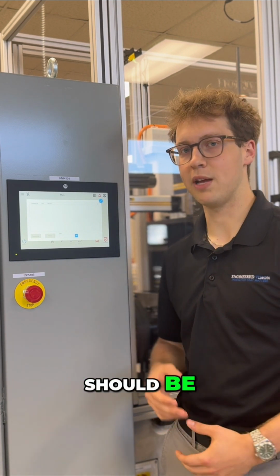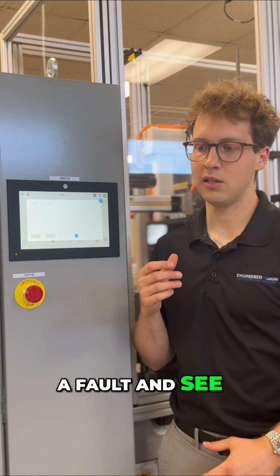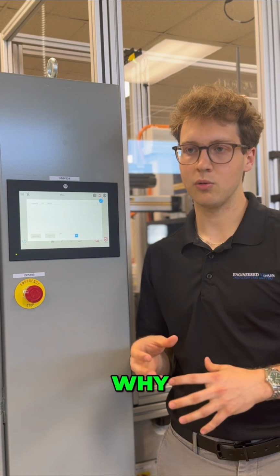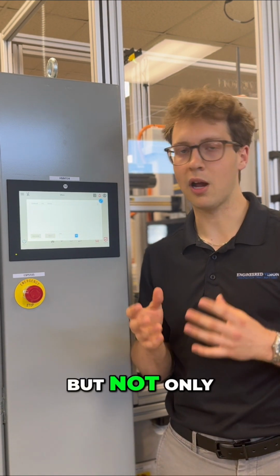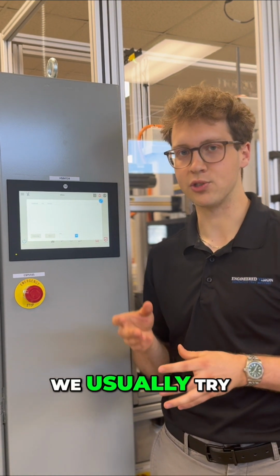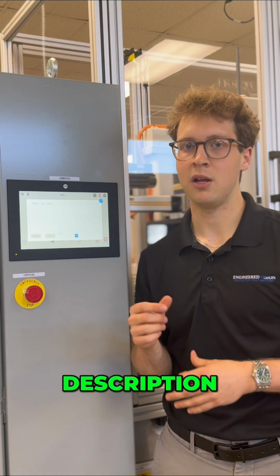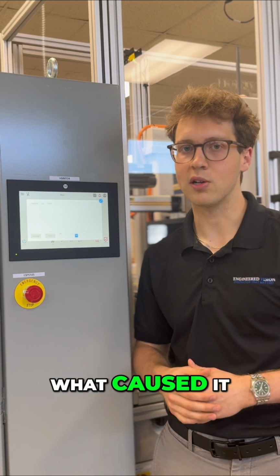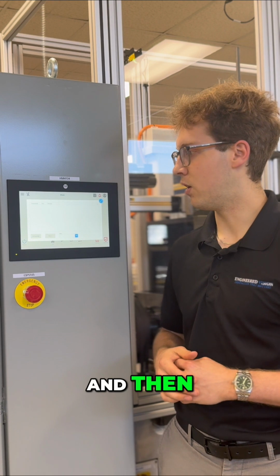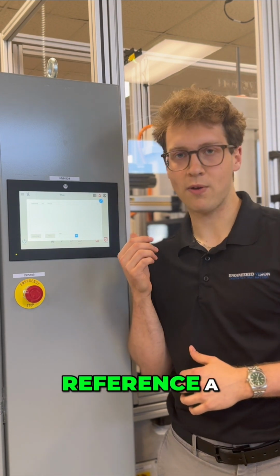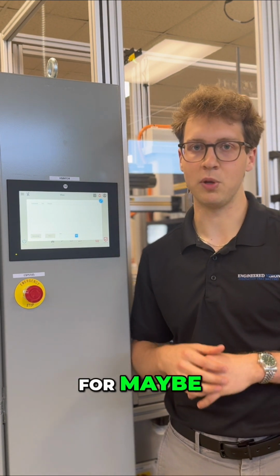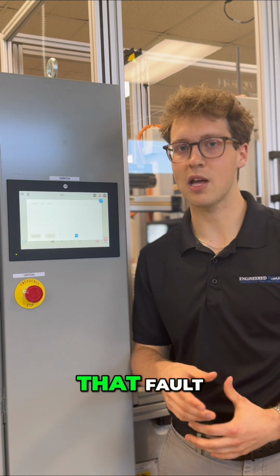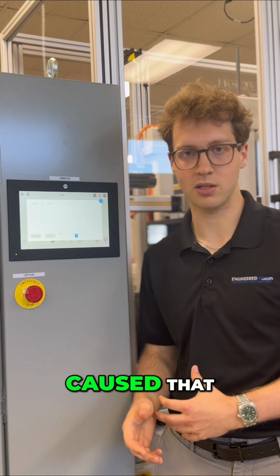The operator should be able to look at a fault and see exactly what the fault is, but not only that, but why the fault happened. We usually try and explain in the description potentially what caused it or that kind of thing. And then we will do our best to reference a wire number as well, for maybe which specific sensor caused that fault, or maybe a component caused that fault.